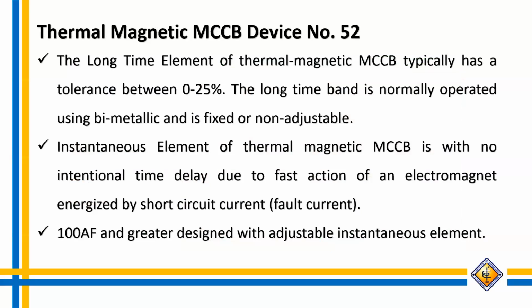Thermal magnetic MCCB is device number 52 by ANSI device. The long time element of thermal magnetic MCCB typically has a tolerance between 0 to 25%. The long time band is normally operated using bimetallic and it's fixed or non-adjustable. The instantaneous element of thermal magnetic MCCB has no intentional time delay due to the fast action of the electromagnet energized by short circuit current. I will just read this quickly so we can proceed to our TCC manual calculation. A 100 ampere frame or greater is designed with an adjustable instantaneous element.